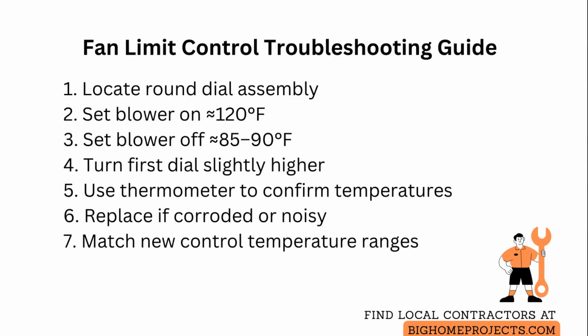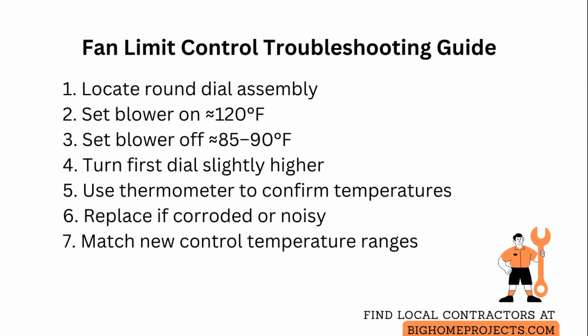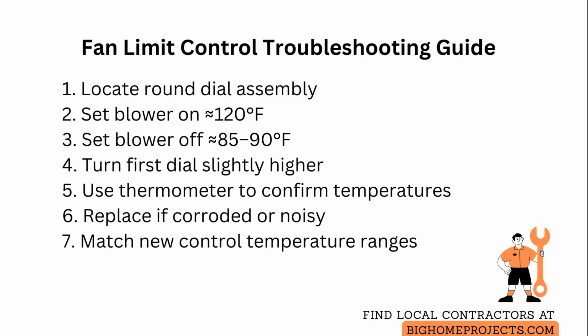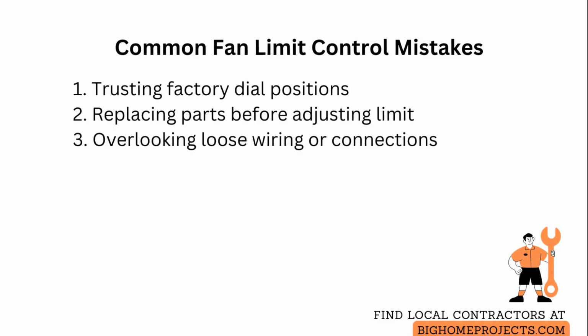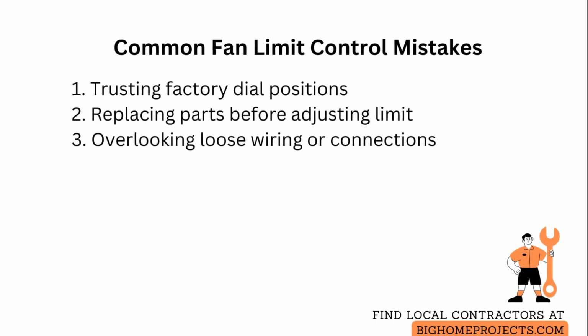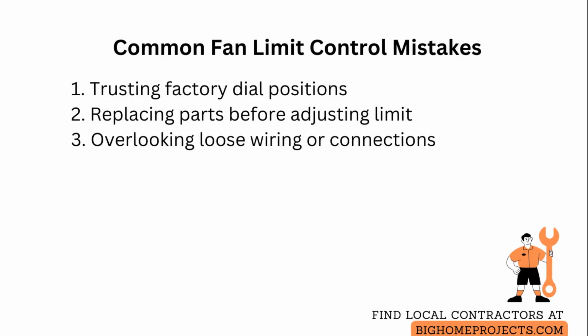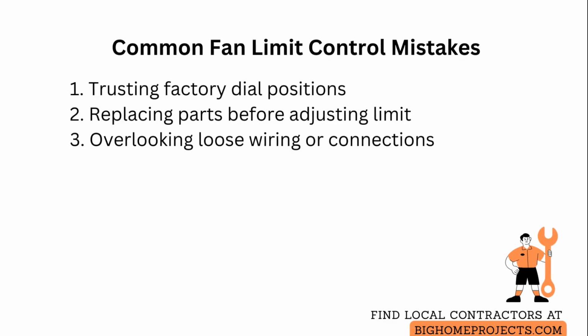When replacing the control, match the temperature ranges stamped on the new control to the old one and shut power to the furnace at the service switch or breaker before making wiring changes. Common mistakes are trusting the factory dial positions without measuring actual temperatures, which can leave the blower running. Fix this by measuring and then adjusting the on and off settings to the recommended ranges.